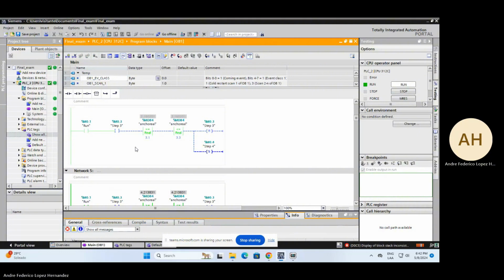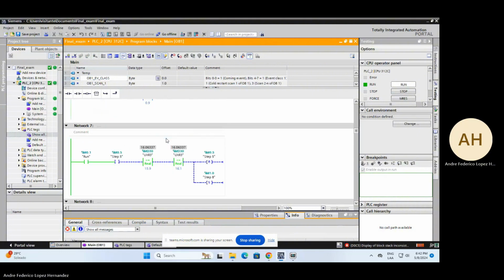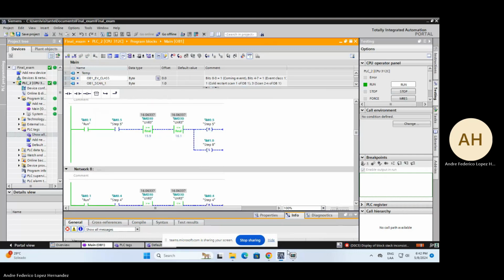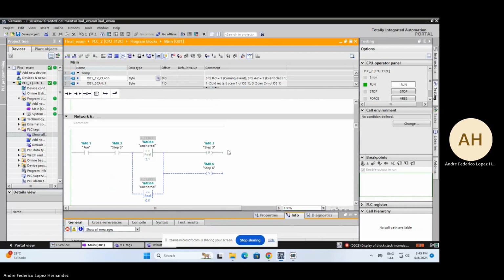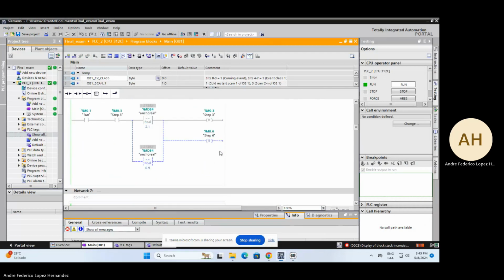Then the system checks if the eject cylinder controls are on during the time the part is being ejected. If run is turned off while the piece is being ejected, the step should be completed before pausing. Also, when the run internal bit memory turns on after the operation is paused, the station should resume the suspended step, and when it's paused, the conveyor should be turned on.